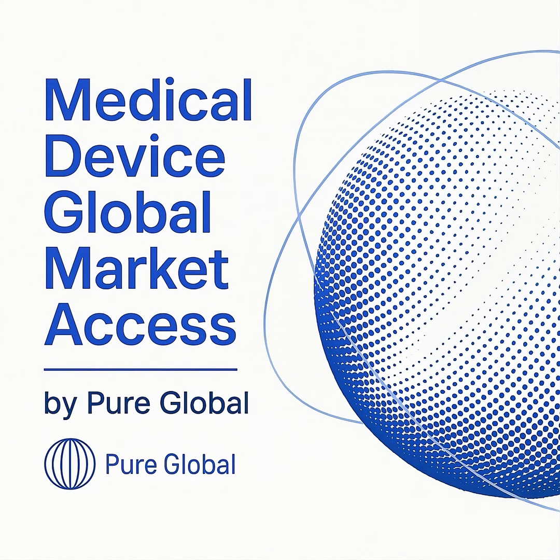So, who needs an MDEL? Importers located in Canada and distributors, whether they are inside or outside of Canada, must hold an MDEL to sell devices of any class. Foreign manufacturers of Class 1 devices who wish to sell directly into Canada also require one. A common exception is for manufacturers of Class 2, 3, or 4 devices. They do not need an MDEL if they are only selling their own products that already have a medical device license, MDL. But the Canadian importer or distributor handling their products must have an MDEL.